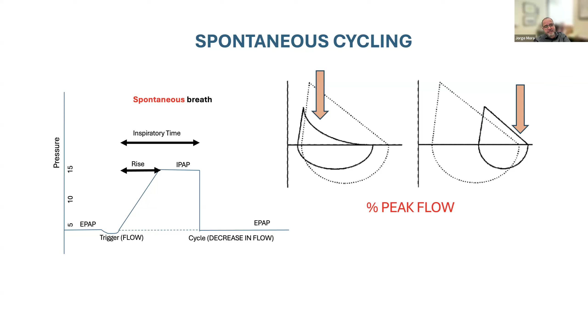This is also a little bit of, and the reason I'm putting this here is because the next slide is going to show something very specific for ResMed devices, but it applies to all other devices. The reason is that spontaneous cycling matters, and it's usually predefined in the device, and this is true. For example, I don't know if you guys have the V60 there. It's also predefined in many devices. For example, the V60 on different modes and on AVAPS, for example, will cycle at 75% of maximum flow.